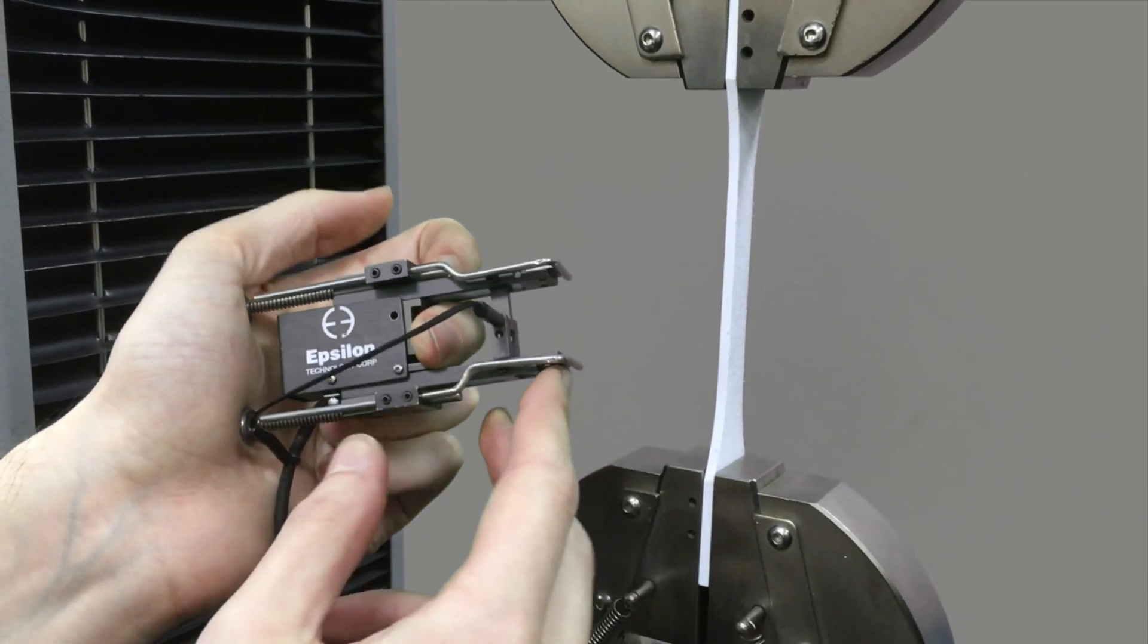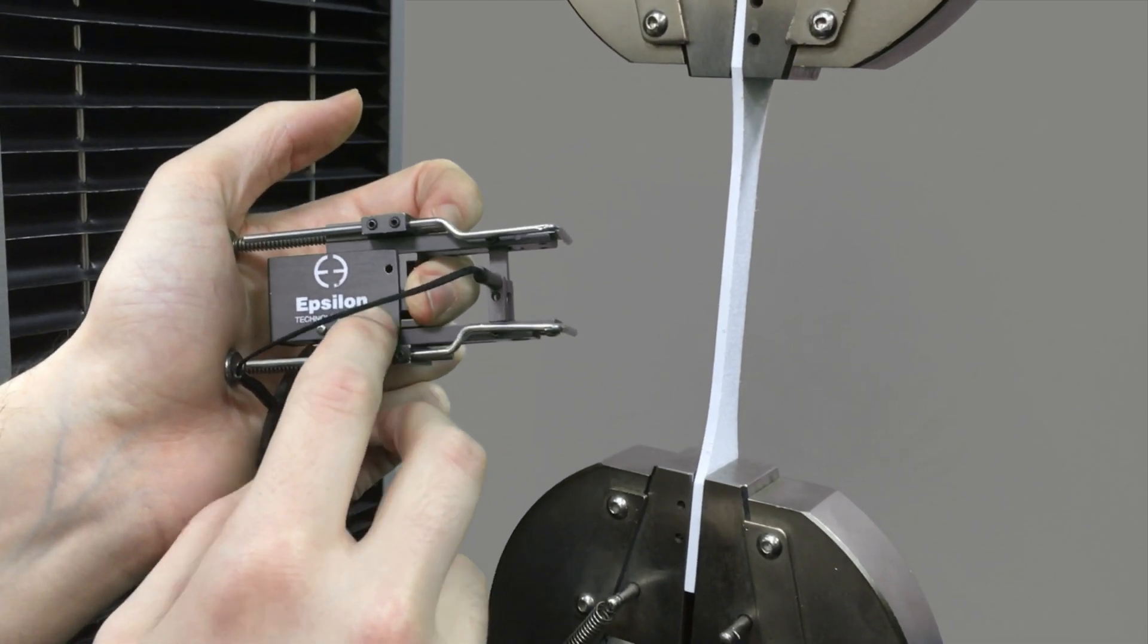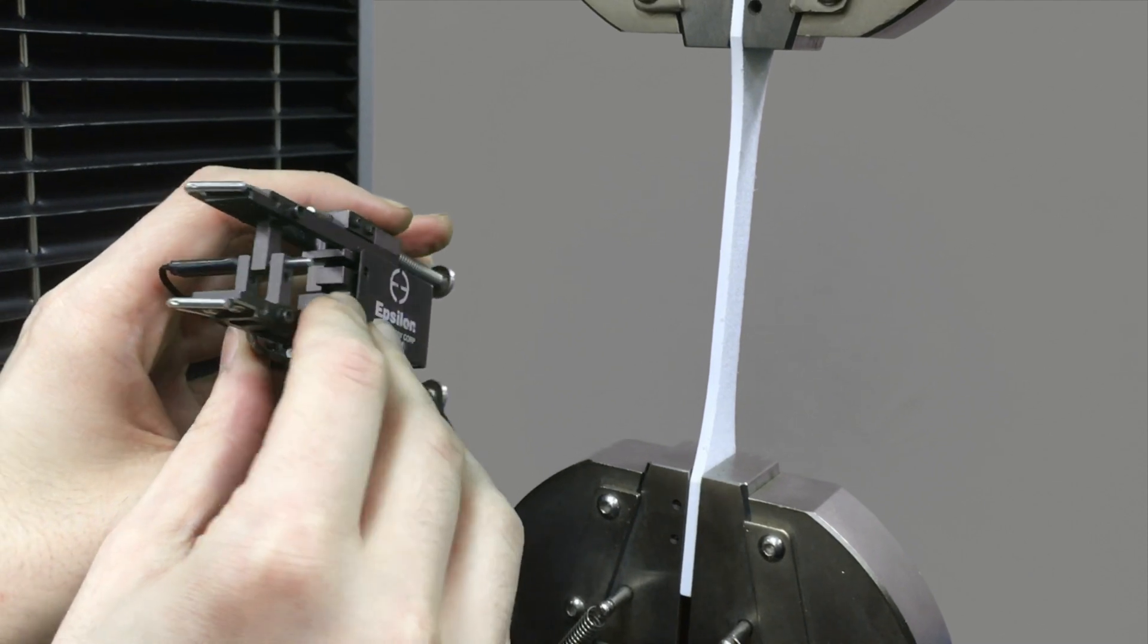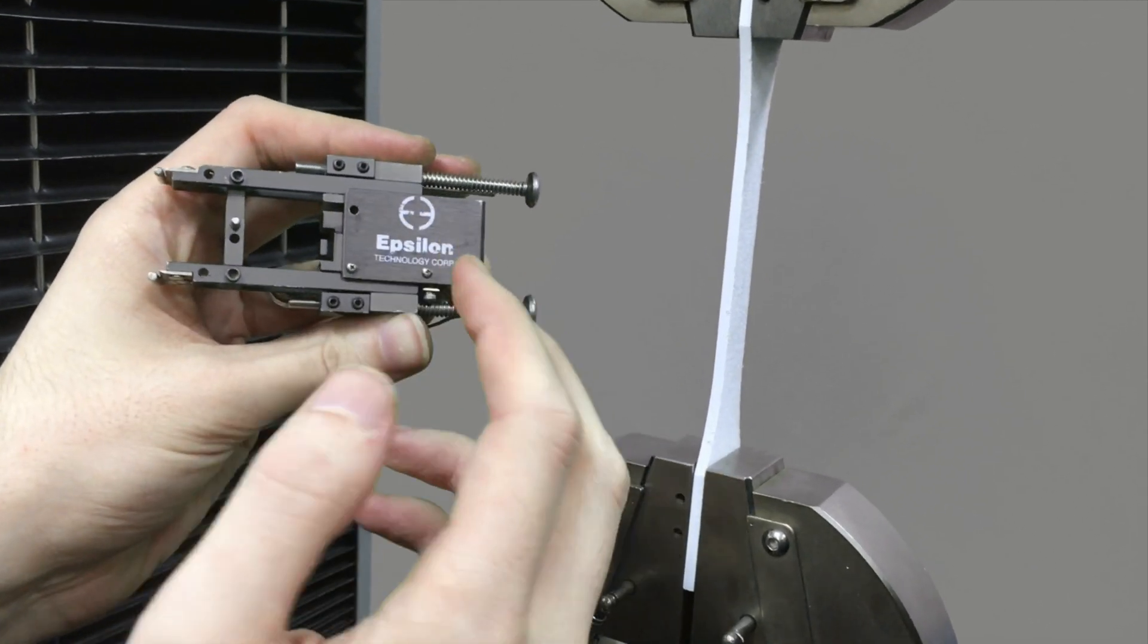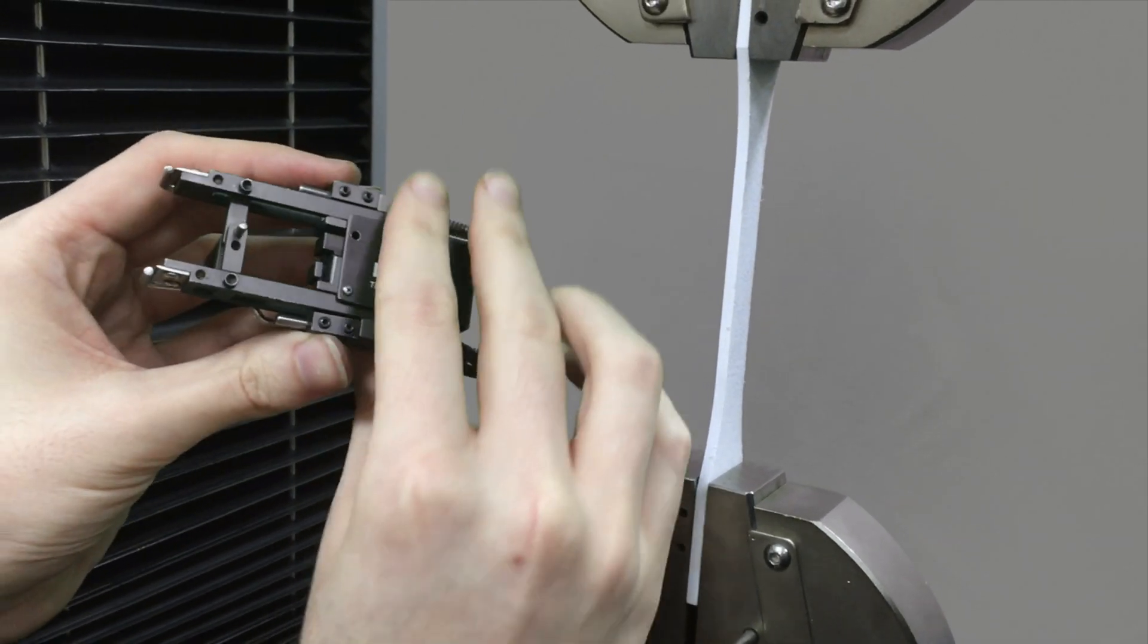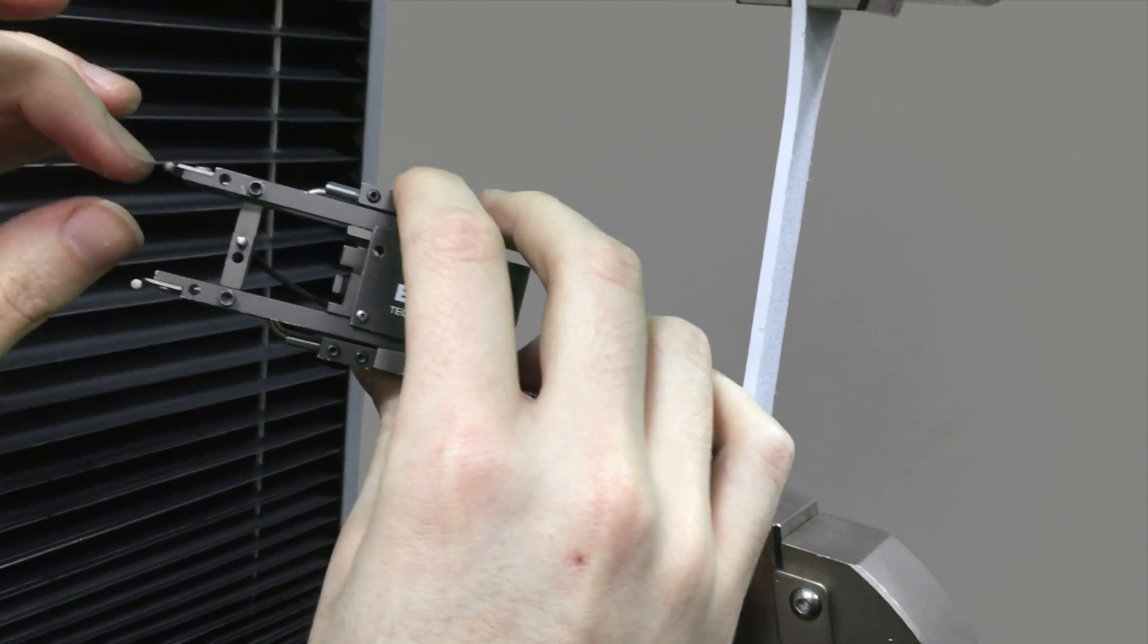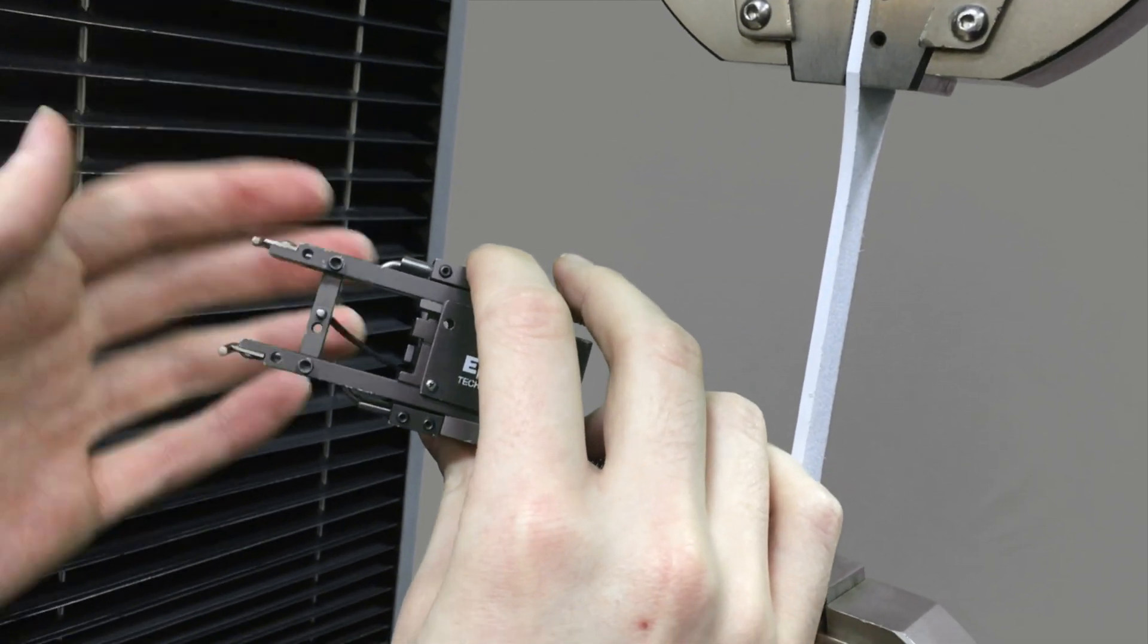Each extensometer is rated for a certain gauge length set by the device specifications. All extensometers have some way of indicating where your gauge length is. For example, you'll notice that this one here has a little pinhole that when you put a pin in there, the teeth are exactly at the gauge length, which in this case I believe is one inch apart.